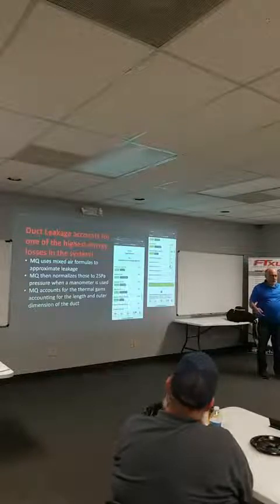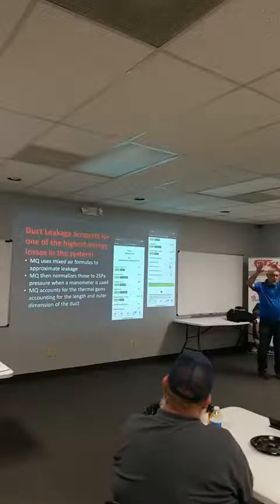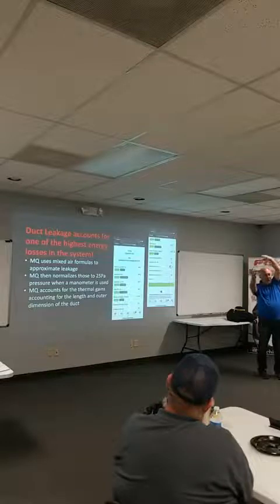I'm going, damn it, my furnace must have shut off. I walk over there, it's got 140 degree air. I put my hand in the duct and it's hot as hell. Go back over and say, well, the thermometer's screwed up. And I couldn't understand what was going on, because I envisioned in my head that that stream of air was just going to shoot across that duct, mix in, and I was going to get a warm mixed air temperature. That stream of air just went right down the backside of that duct, straight as could go, and it only went out about 6 inches, the width of the supply duct.